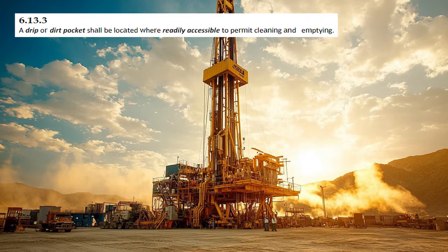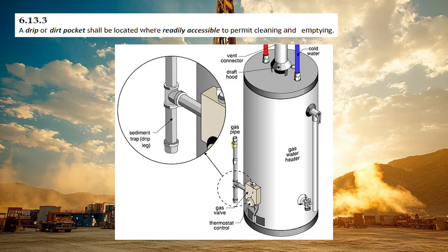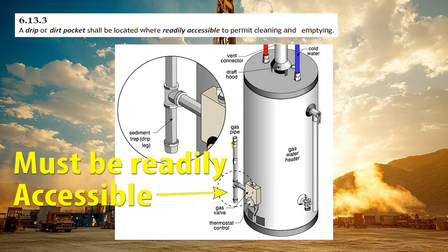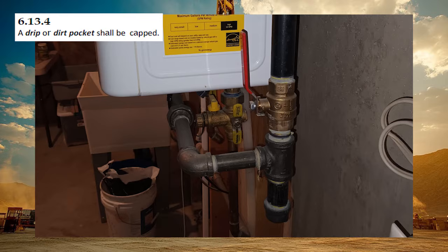The next clause I want to cover is clause 6.13.3. A drip or dirt pocket shall be located where readily accessible to permit cleaning and emptying. In short, this means it cannot be concealed. It needs to be accessible at all times so you can take it out and dump it out. Next clause, 6.13.4. A drip or dirt pocket shall be capped. This is an easy one. Put a cap on the bottom of it just like this nipple and cap that you see right here.